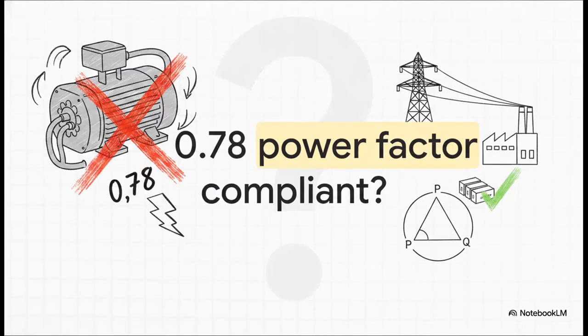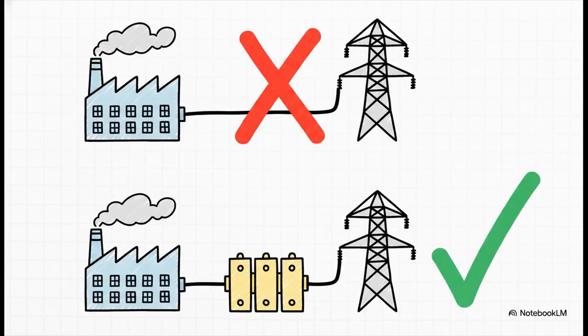Let's actually test this with a quick real-world scenario. Imagine you're inspecting a proposed connection for a high-voltage industrial consumer. They're planning to run some heavy, uncorrected induction motors, drawing current at a power factor of 0.78. So, quick check. Would this connection get approved for energization under the transmission code? The answer is a definitive hard no. 0.78 falls well below that strict 0.85 consumer floor we just talked about.